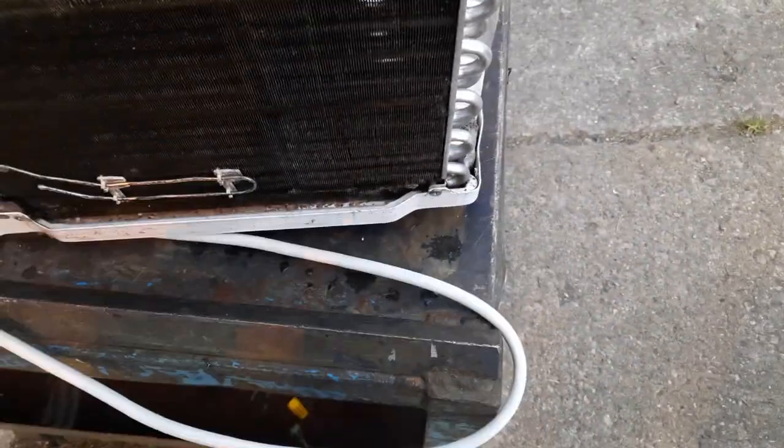I'm more worried about getting... Oh, I got that mystery sludge all along in there, too. Coil's nice and clean on here. The back coil, it's caked. So that's gonna need a lot of cleaning. If I had coil cleaner, it would be an easy process to spray it on, rinse it off, and it'll be fine.